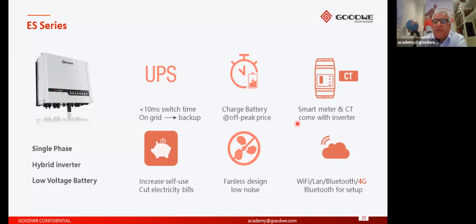If the grid fails, within 10 milliseconds it switches to backup. You can charge the batteries from the grid if required, but in the UK on the DC side we don't actually do that. In other markets, where people know the grid will fail the following day and they've had a bad PV day with not enough charge in their batteries, they can charge their batteries from the grid and have it ready for when the grid fails. All our products come with a smart meter.